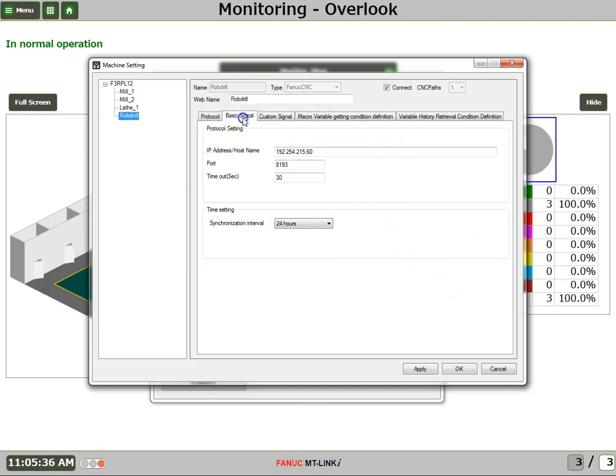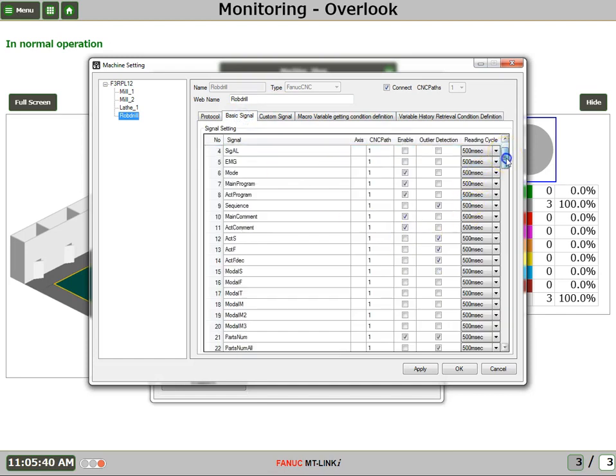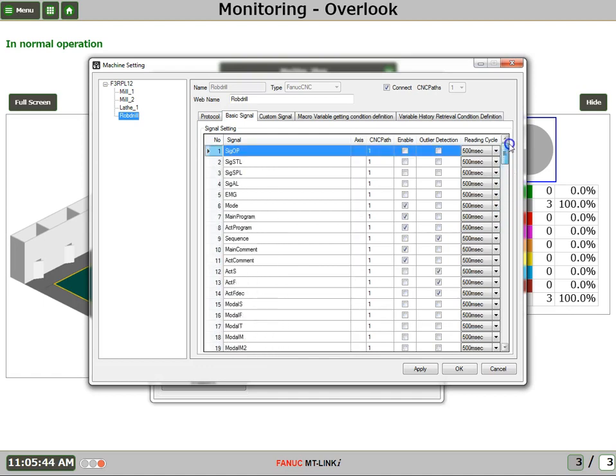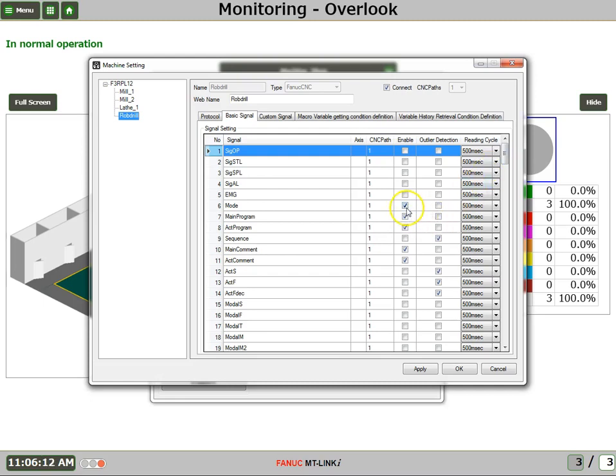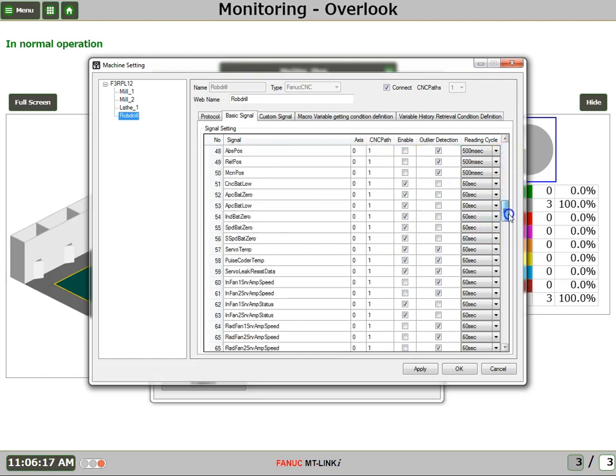At this tab, this is the basic signal. This is part of the beauty of MT-Link-I, is that most everything is configured out of the box, which alleviates the need to really know all the different signal definitions and which to pick and choose. There are 42 signals related to the CNC itself, and for every servo motor, there are 57 signals available. However, for the CNC, 18 are already set as the default to enable. And for the servos, there are 29 that have been default enabled.